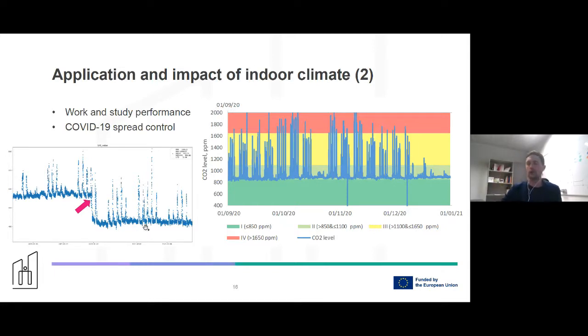And then when we do automated or just CO2-based indoor climate assessment, how do we use this data? So this is basically actually auto-calibration of the sensor. It just manipulates its values so that the minimum values are around 400, which is the outdoor level.